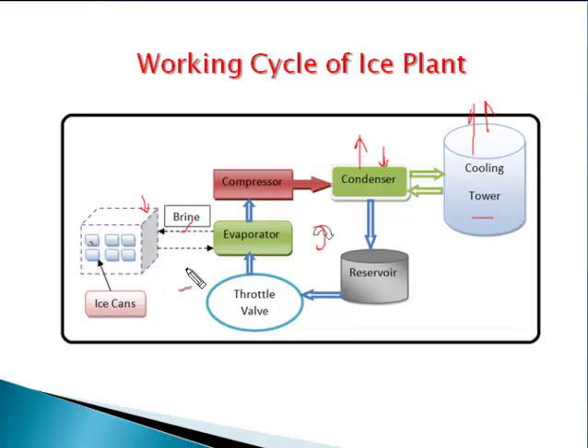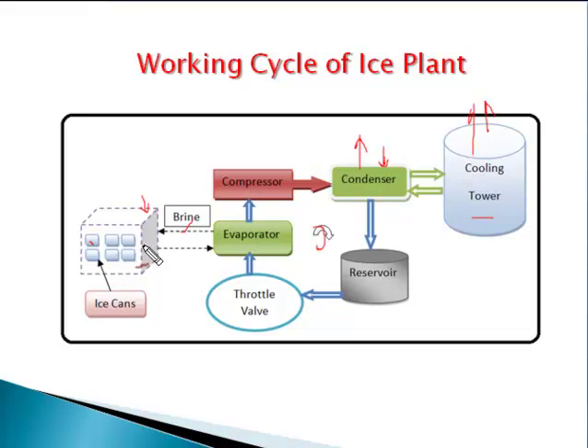We are using brine solution as the cooling medium because when using air as the medium we get less heat transfer. Inside the chilling tank we also use an agitator or propeller which creates continuous motion of the brine solution, so heat transfer takes place in convection mode. The brine solution always moves inside the chilling tank, and heat transfer from the ice can to the brine solution takes place by convection.